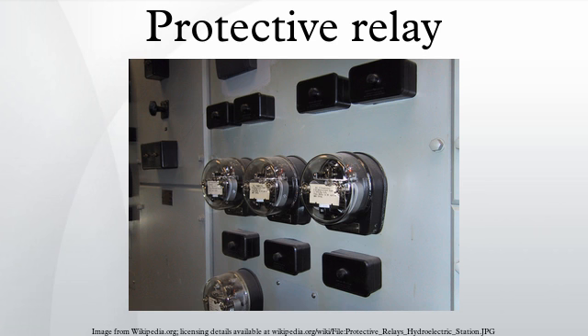In a large installation of electromechanical relays, it would be difficult to determine which device originated the signal that tripped the circuit. This information is useful to operating personnel to determine the likely cause of the fault and to prevent its reoccurrence. Relays may be fitted with a target, or flag unit, which is released when the relay operates, to display a distinctive colored signal when the relay has tripped. Types according to construction: electromechanical relays can be classified into several different types as follows.